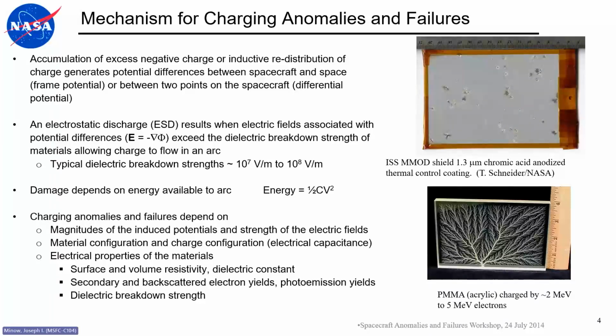If you're just using generic breakdown strength values and don't have a spec sheet from a manufacturer, you ought to look up and measure the actual dielectric breakdown strength, because it might be lower than you thought.